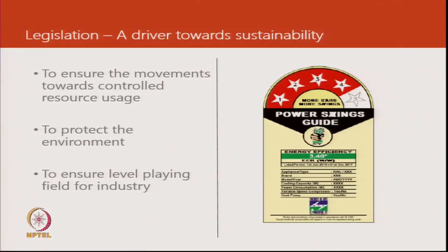It's the ratio of cooling at standard conditions. All air conditioners need to go through a balanced ambient calorimeter test to define performance at a particular standard: outdoor temperature of 35, indoor conditions of 27 degrees dry bulb and 19 wet bulb. The air conditioner is tested to demonstrate that it complies with what is on the label within 5%.